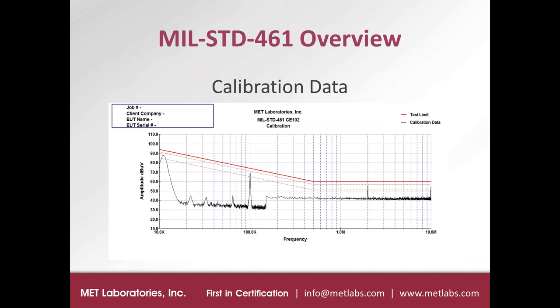This is a plot of the calibration data. And the way that we set up our plot is to have some dotted guidelines. One of them is 3 dB higher than what we're shooting for, and one of them is 3 dB lower, so that we can easily see that the calibration signals fall within the plus or minus 3 dB tolerance. And this plot would represent a calibration that passed or that was compliant. We could move on with the test.